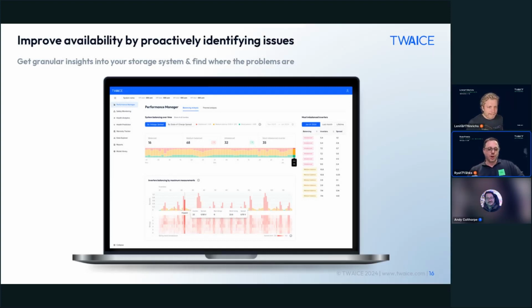This is a view of our web platform and our Performance Manager suite. The entire point is to pinpoint where problems are occurring. The delta here is, it's one thing to know on a system level basis, as individual bar lines that Leonard was talking about in those previous slides. It's an entirely different thing to dive into correlations between the TWAICE-calculated state of charge and the other KPIs we're looking at, temperature, voltage, DC resistance, and others, to be able to say, at a very granular level, this particular element of the DC storage block is causing the issues, and trigger a long-term service agreement clause or other remediation action.